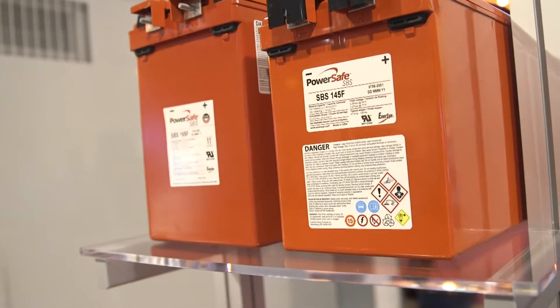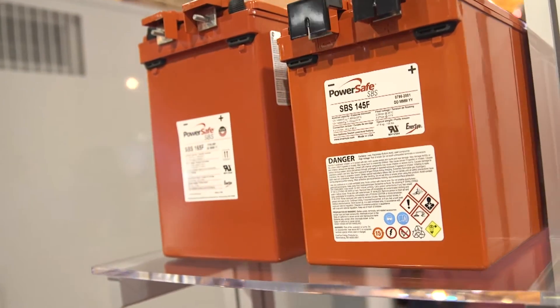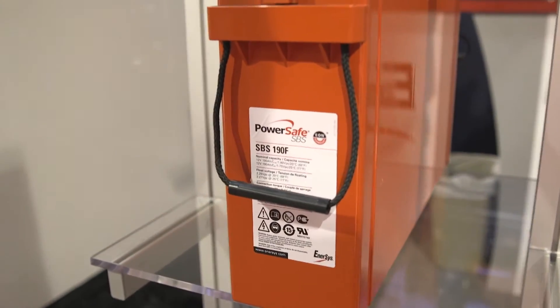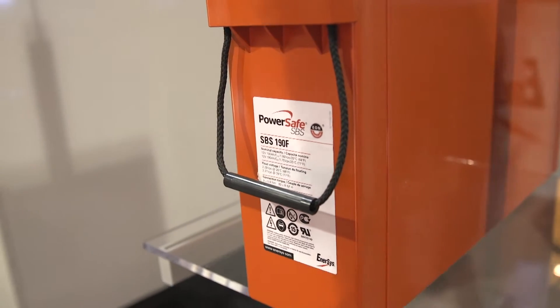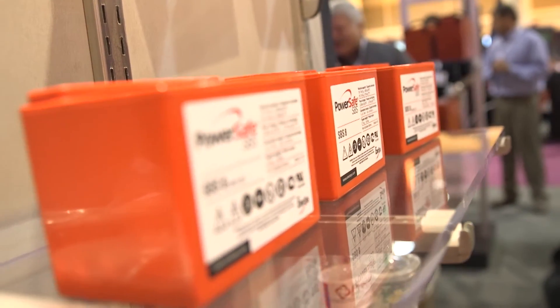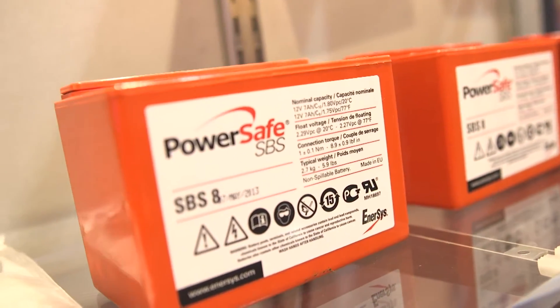That battery gave very good power density as well as a very long life. Unfortunately when you grouped more than one cell together you lost a lot of efficiency because of all the empty space. About 20 years later, another company in the Enersys group produced a flat plate technology using thin plate pure lead. Pure lead means low corrosion, low gassing, low float voltage — resulting in a battery that outperforms anything else out there.